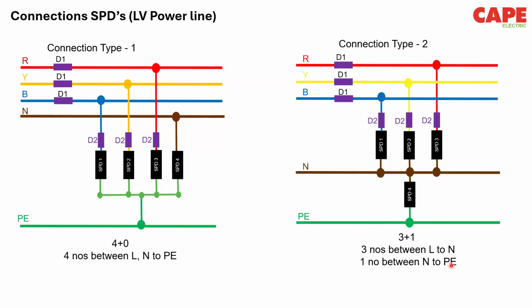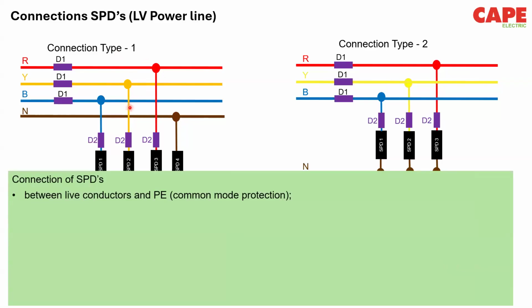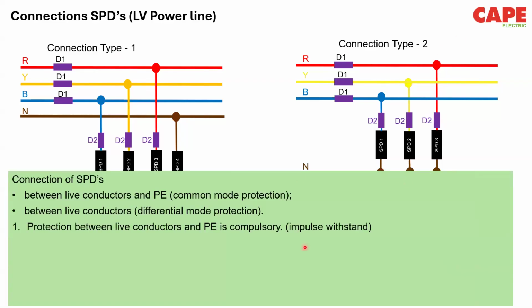Obviously, both these connection types have their own advantages and disadvantages, which I will explain. For example, connection between line conductors and PE conductors, which is connection type 1, the 4+0 connection, is called common mode protection. We are expecting surges between line and PE. Connection type 2 is called differential mode connection. It is between phase and neutral to earth. So, as per 60364 standards, protection between line conductor and PE is a mandatory requirement. It is called impulse withstand and it is mandatory.